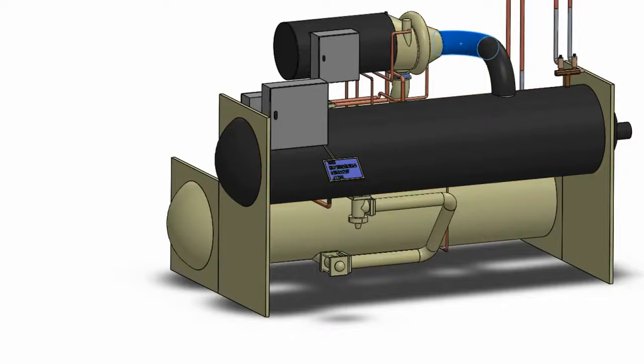So the evaporator needs to have a certain amount of liquid refrigerant in it for sufficient heat exchange to occur. If there's a lot of superheat coming from the evaporator, then that means there's a lot of vapor in there, and that means there is not enough liquid refrigerant in the evaporator, so more needs to enter. So the expansion valve is keeping that balance between the right amount of liquid refrigerant and the right amount of superheat. You only want vapor entering into the compressor.